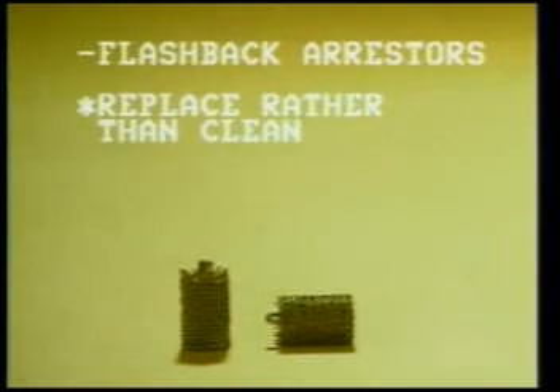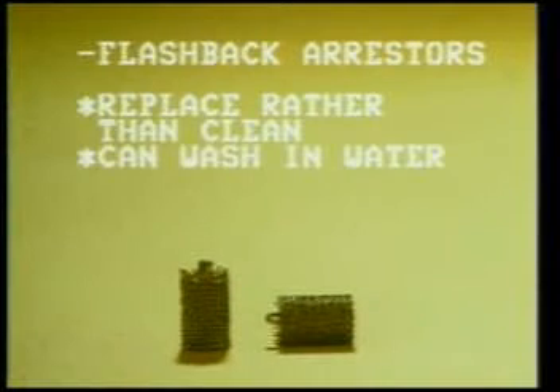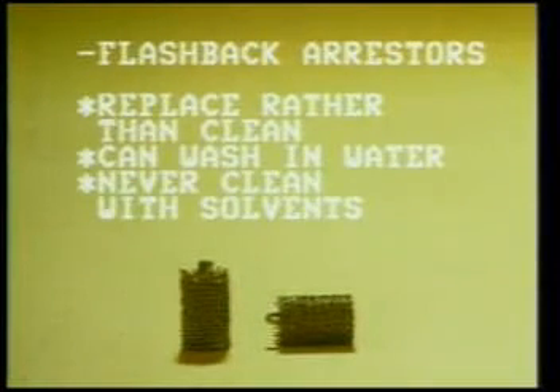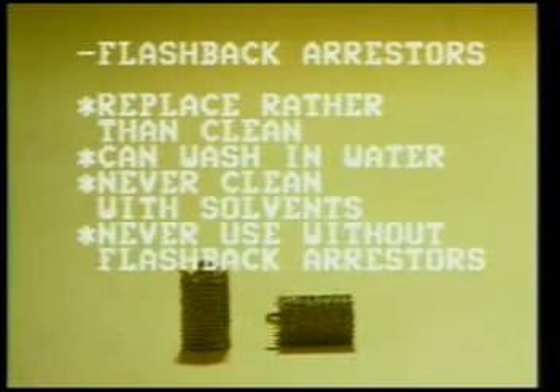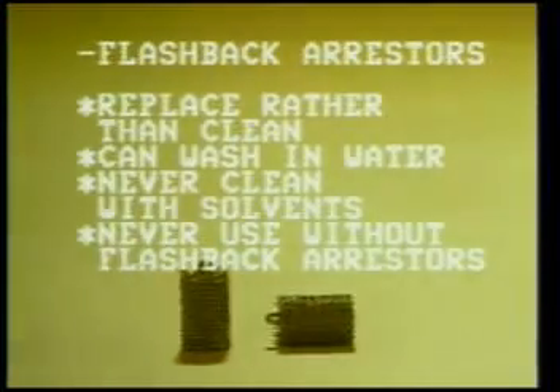However, if you can't get a replacement immediately, they can be washed in water and dried thoroughly. Never clean them with solvents. Remember, the explosimeter indicator must never be used without the flashback arresters, because they prevent the combustion that may occur in the instrument from reaching the hazardous atmosphere or the area where you're standing.